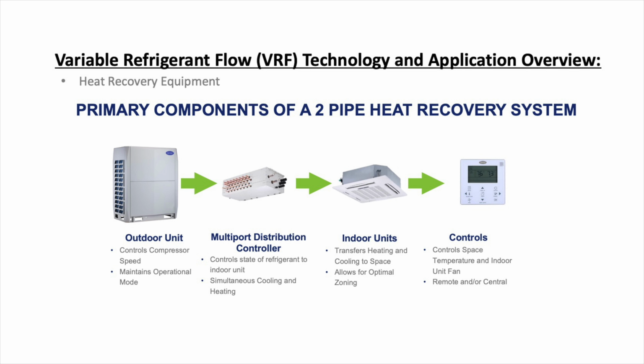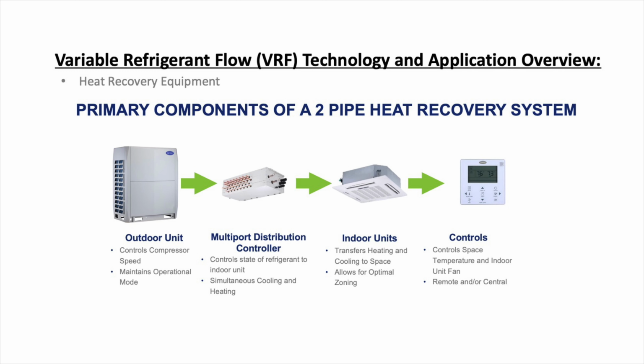Here's a 2-pipe heat recovery system. So this would be similar to a Trane Mitsubishi or a Carrier 2-pipe heat recovery system. All the components are the same, but on this Carrier 2-pipe heat recovery system, you have your multi-port distribution controller, and this is what controls the state of refrigerant to the indoor unit.